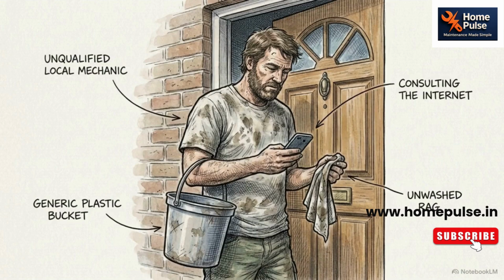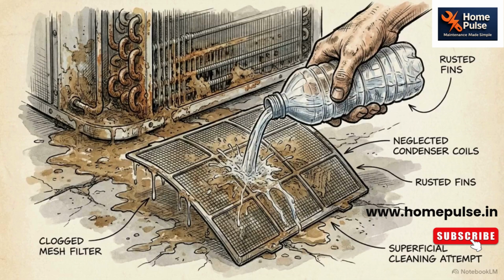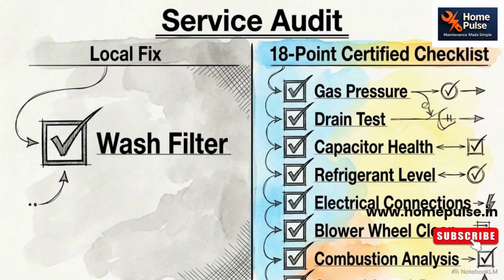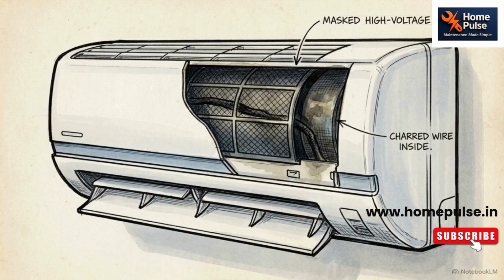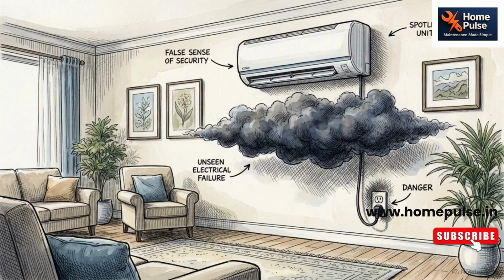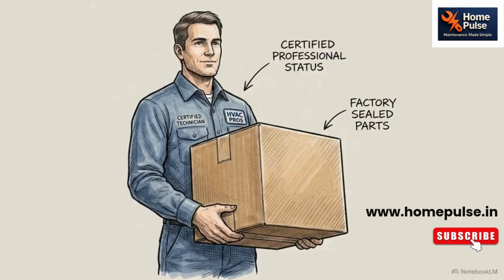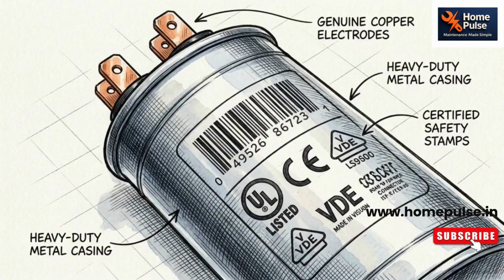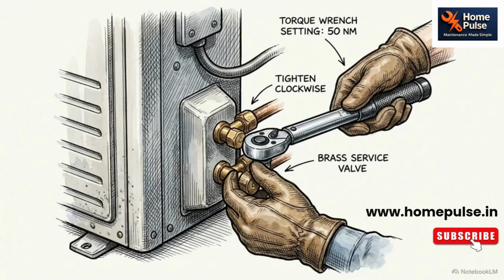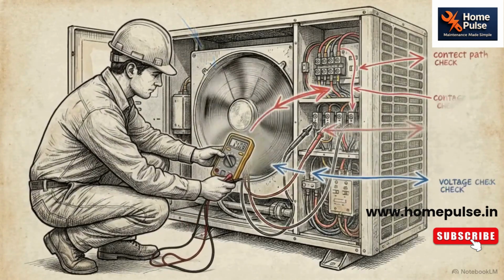So when it's time to fix these issues or perform maintenance, a local mechanic will usually show up, wash the dust off the filter, spray some water, and call it a day. A genuine, certified safety audit is completely different. It requires testing gas pressure, inspecting wire gauges, and verifying MCB health. That superficial wash actively masks internal electrical degradation. It leaves you with a clean-looking machine and a completely false sense of security. Certified technicians use genuine replacement parts instead of temporary workarounds, directly addressing the core mechanical faults before they fail. A premium service provides a verifiable safety audit of a hazardous appliance, ensuring the system is mechanically sound rather than just blowing cold air.